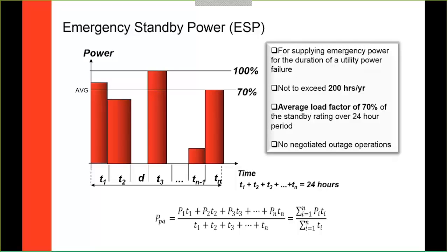So it's important to understand just what I was talking about in relation to warranty. The expectation from ISO is that this typically is not used for more than 200 hours a year, but there's an understanding that this is intended for usage during emergency applications that may exceed that timeline. So again, make sure to work with your generator set manufacturer to understand what that means for your customer.